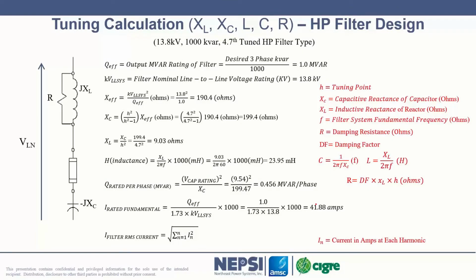So for a high pass filter, the beginning calculations are exactly the same. The key difference is how we handle the damping factor. But the tuning calculation is exactly the same. The value coming up with X of C is exactly the same, and more or less coming up with the ratings for X of L is exactly the same. What changes here is the damping factor that we come up with.